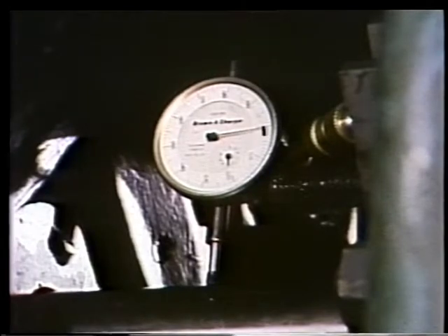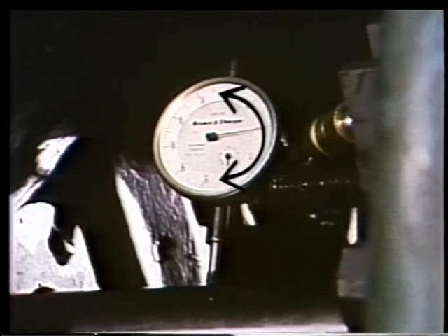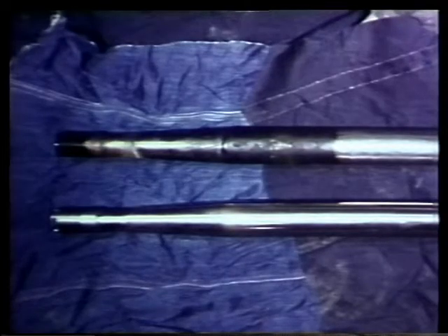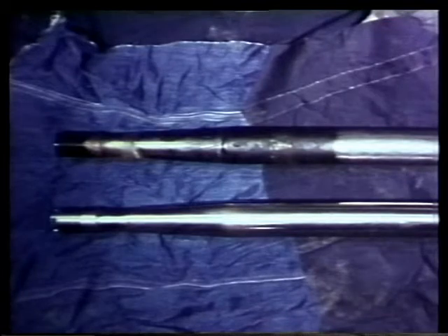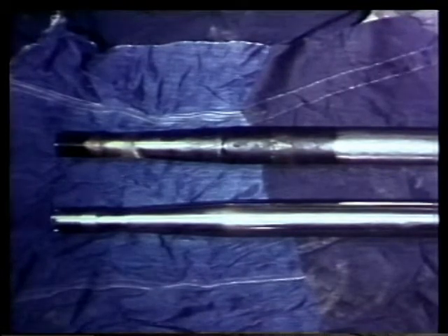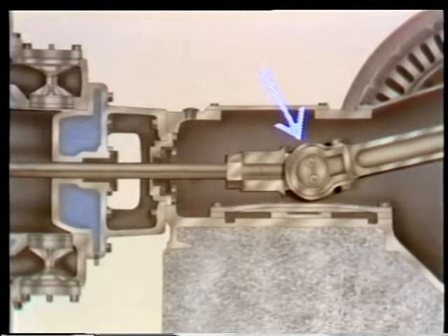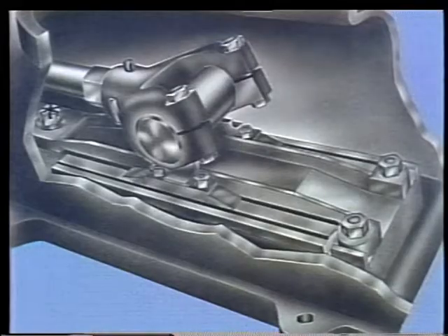If the piston rod is tilted, the reading will either increase or decrease as the piston moves through its upstroke and return to zero as the piston moves through its downstroke. Now, if the rod is bent, the change in the reading is a little different. The reading will both increase and decrease as the piston moves through its upstroke. A bent piston rod must be replaced. But if the piston rod is tilted, you must adjust the position of the crosshead until the rod is no longer tilted.